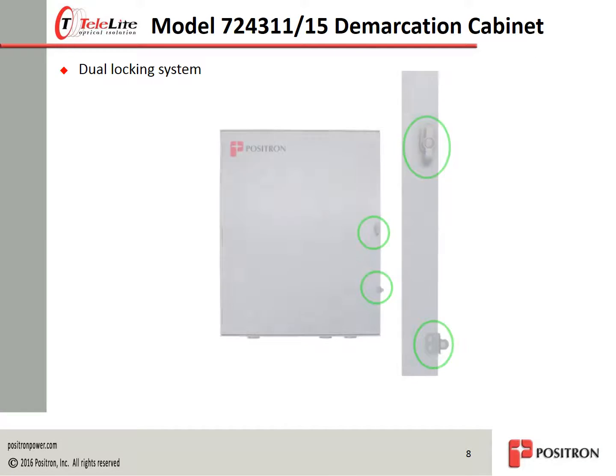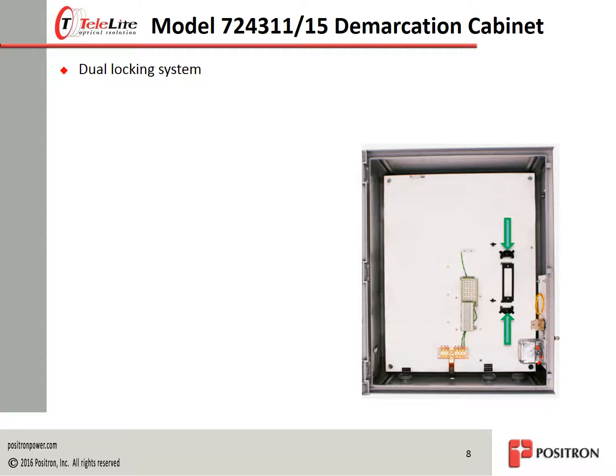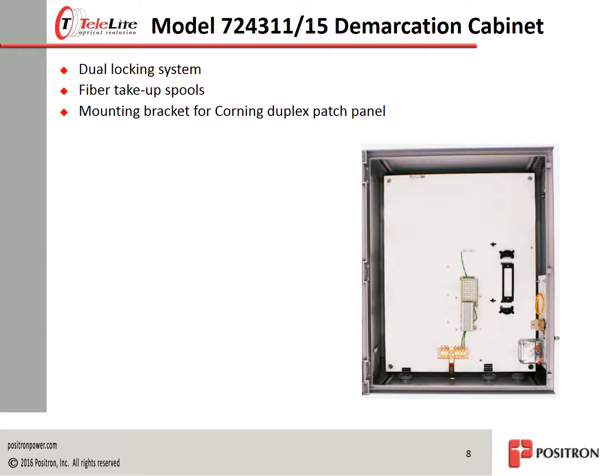Positron's demarcation cabinets offer a dual locking system for increased security. One padlock can be used to secure the cabinet doorknob, and a second padlock locks the custom-made heavy-gauge stainless steel hasps integrated into the convolutions of the cabinet's door frame and seal. In the right-hand portion of the demarc cabinet backboard are two fiber take-up spools and a raised steel bracket used to mount a Corning duplex patch panel to help manage the power company's dielectric fiber span from the demarc cabinet into the substation control house.